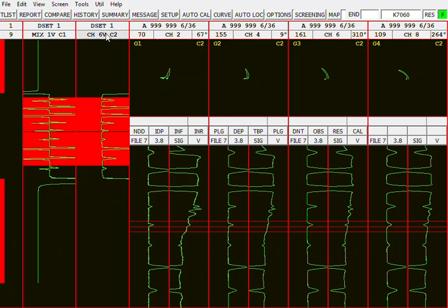Because it's a lower test frequency, it also allows you to see the structures in your heat exchanger easily, so you can tell where you're at. And when you can detect structures easily, it also helps you assign locations to each one of those signals. So during your reporting, you can report where a flaw is next to, like the second support plate plus 12 inches or whatever.